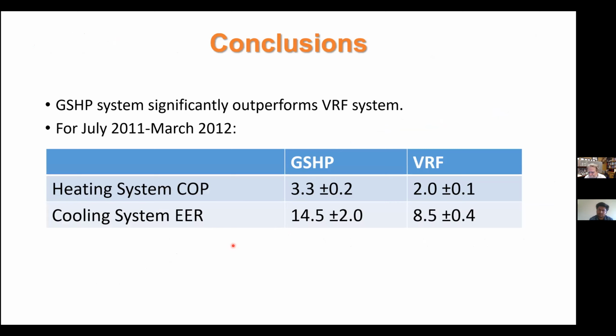So in terms of conclusions, the ground source heat pump system significantly outperformed the VRF system. For the 9-month period where we could compare them, you can see that the ground source heat pump system had over 50% higher heating COP. And I think it was something like 60-some% higher. I'll try to do the math in my head, but it's quite a bit higher EER than the VRF system.